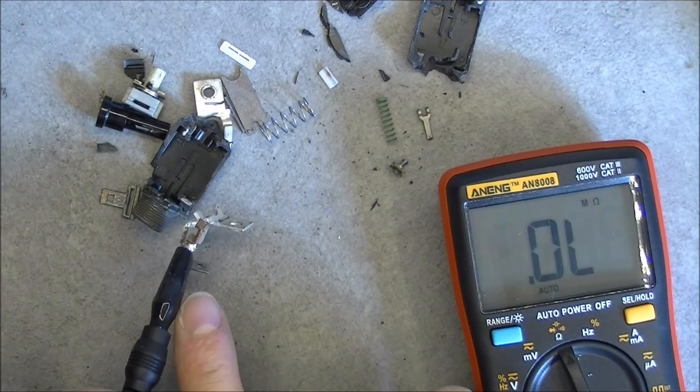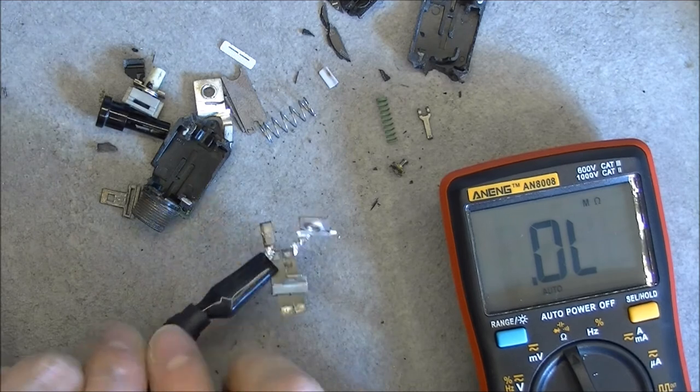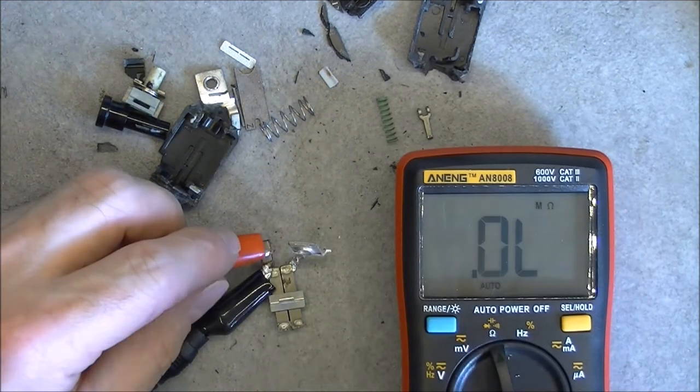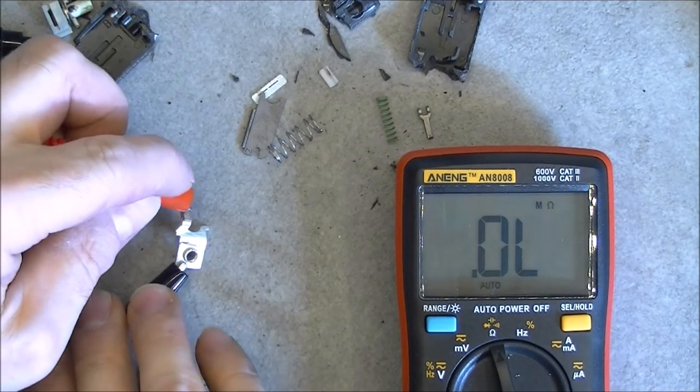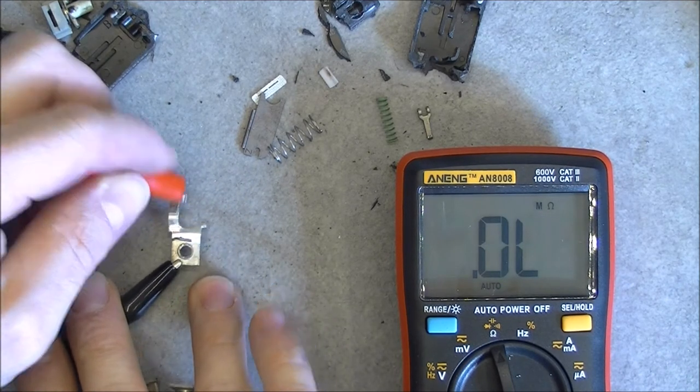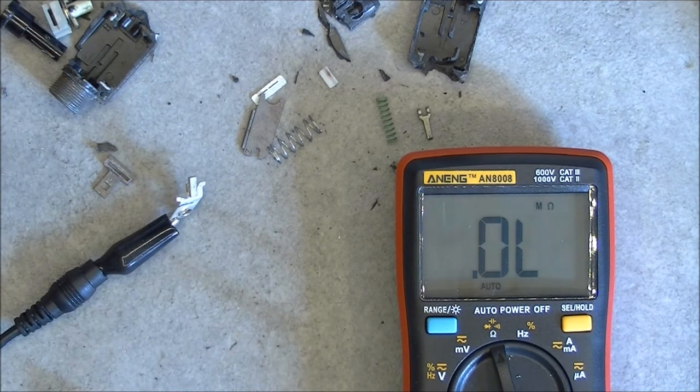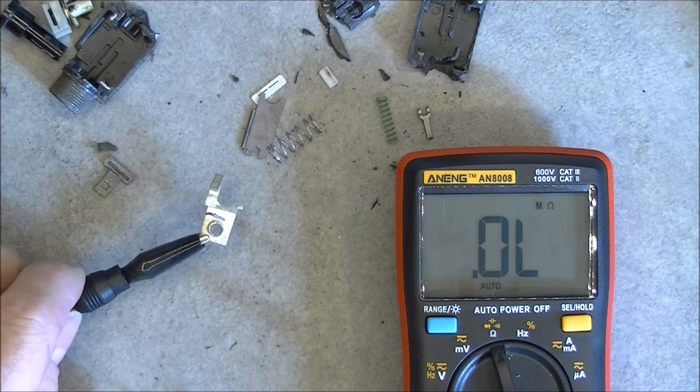Somehow this metal pad here oxidized or something, and it is showing very high resistance. I will check the other one here. It is the same. Really weird. Now what I need to do, of course, is try to clean them and see if the problem disappears.